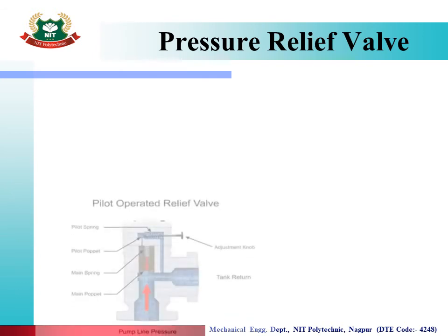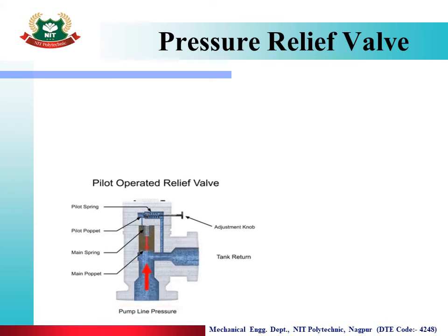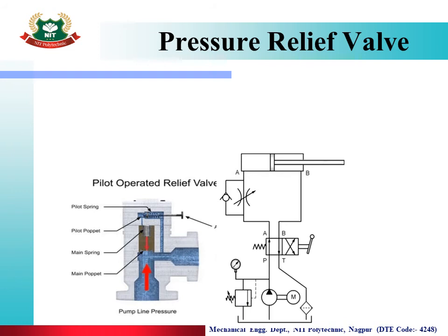Pressure Relief Valve: the name indicates its function — it relieves or releases pressure whenever it exceeds the set limit. In the animation, fluid comes from the pump line; when pressure rises, the valve shifts upward and return line flow goes back to tank. You can adjust the pressure setting with an adjustable knob. The valve components are: main poppet, main spring, pilot poppet, pilot spring, adjustable knob, and tank return line.